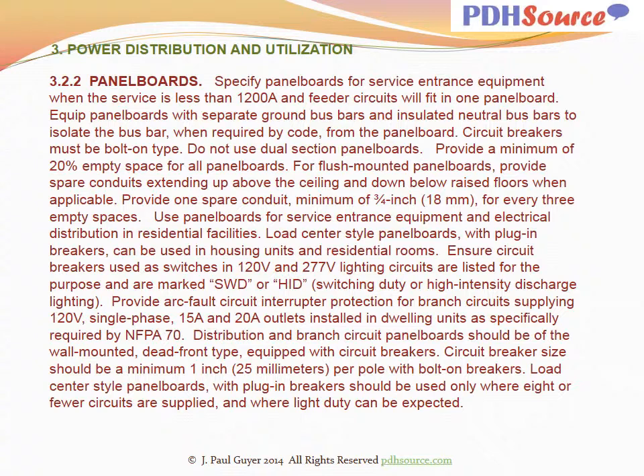Provide arc fault circuit interrupter protection for branch circuits supplying 120 volt single phase 15 amp and 20 amp outlets installed in dwelling units as specifically required by NFPA 70. Distribution and branch circuit panel boards should be of the wall mounted dead front type equipped with circuit breakers. Circuit breaker size should be a minimum 1 inch per pole with bolt on breakers. Load center style panel boards with plug-in breakers should be used only where 8 or fewer circuits are supplied and where light duty can be expected.